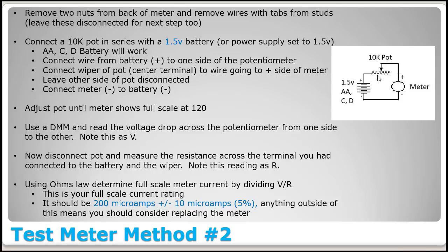When you do this, make sure the pot is in the middle when you start, and you're basically going to adjust it until the meter shows full scale at 120. Then you're going to use your digital multimeter and read the voltage drop across this potentiometer. That would be from this point right here to this point right here, not from one end of the pot to the other. So you'll go from the left lug that you connected here to the center tap, measure the voltage drop there with all this connected and the meter at 120, and write that value down as V.